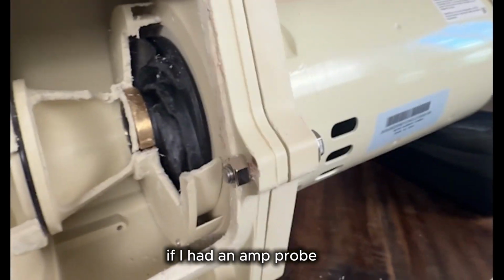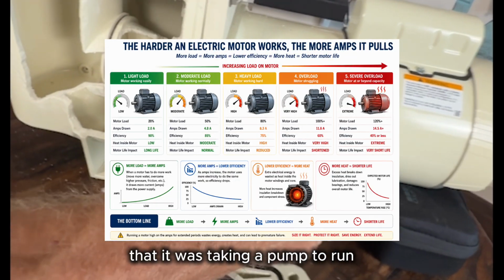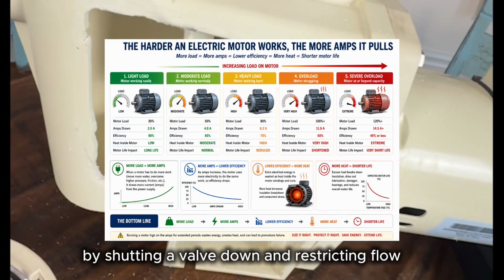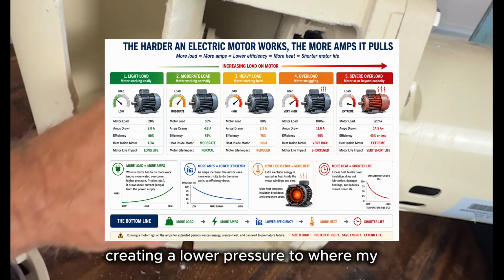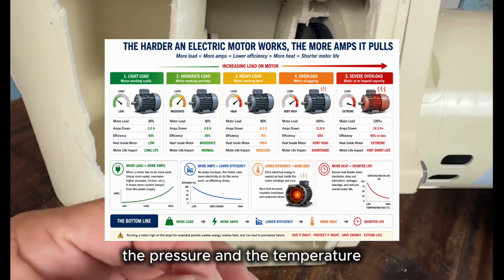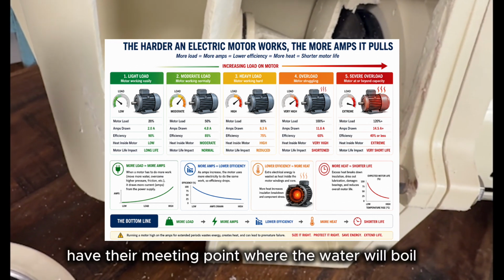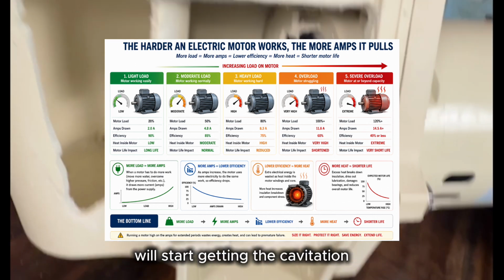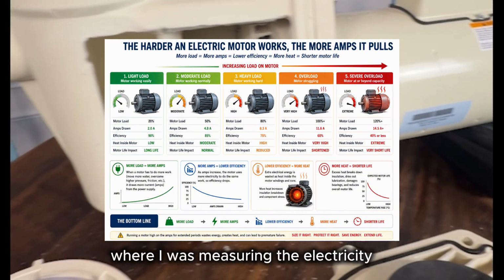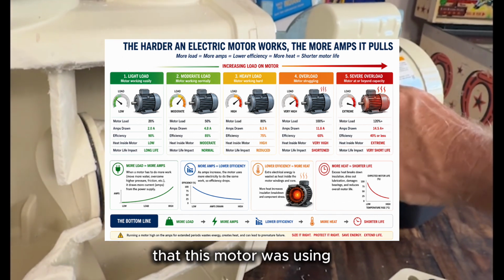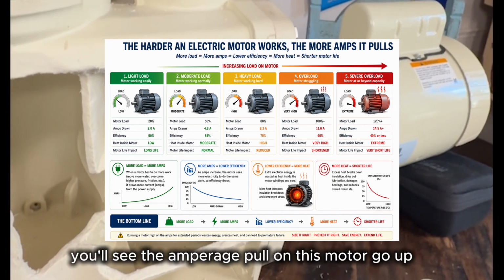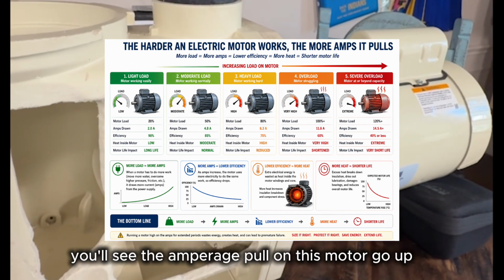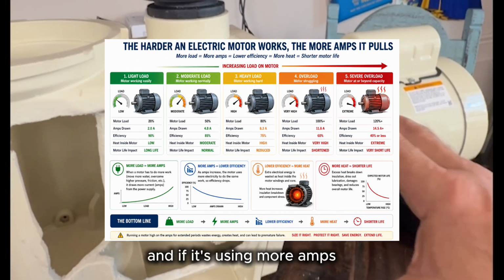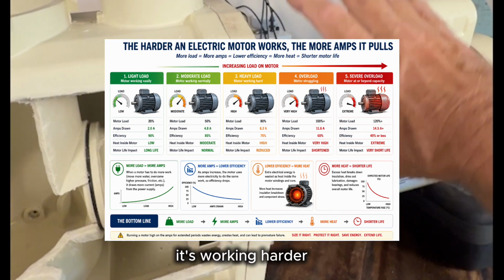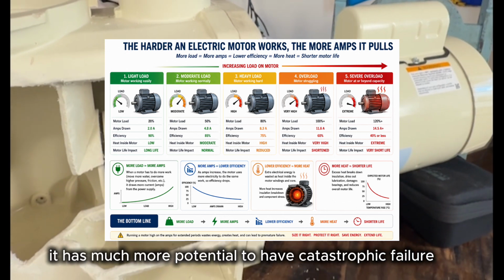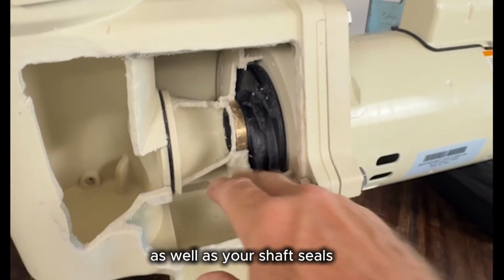If I had an amp probe and I was measuring the electricity it was taking for the pump to run, and I caused cavitation by shutting a valve down and restricting flow, creating a lower pressure to where the pressure and the temperature have their meeting point where the water will boil, we'll start getting the cavitation. Then you'll see the amperage pull on this motor go up, and it can go up significantly. If it's using more amps, that means it's creating more heat, it's working harder, and it has much more potential to have catastrophic failure and cause your motor to fail, as well as your shaft seals.